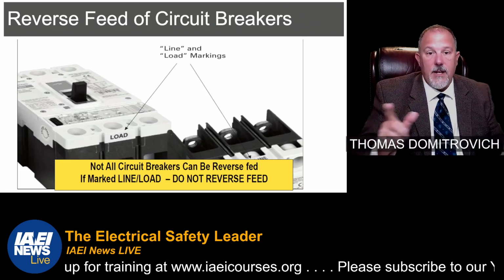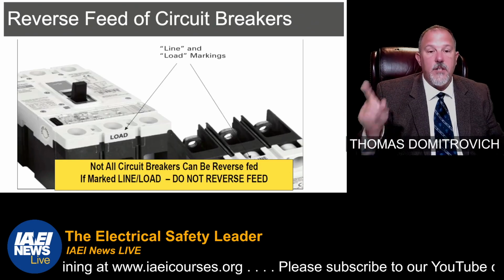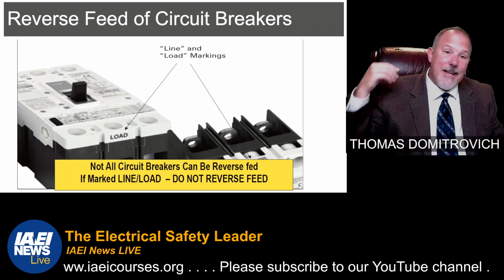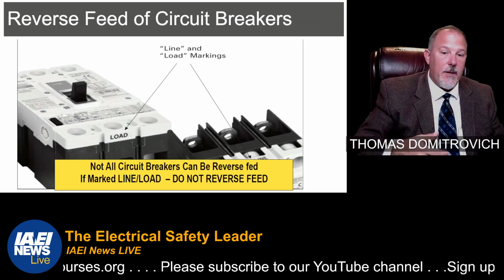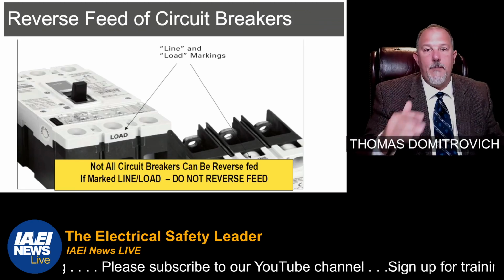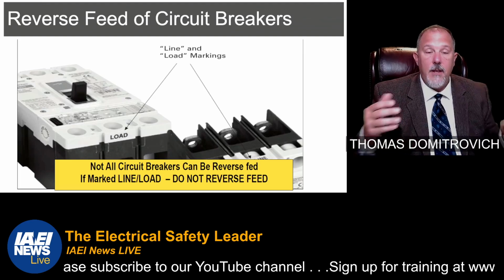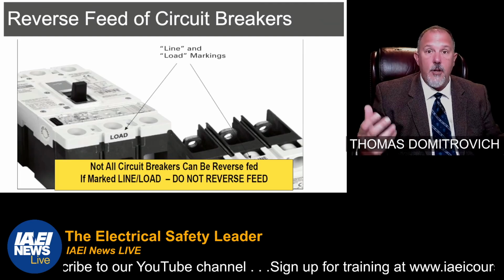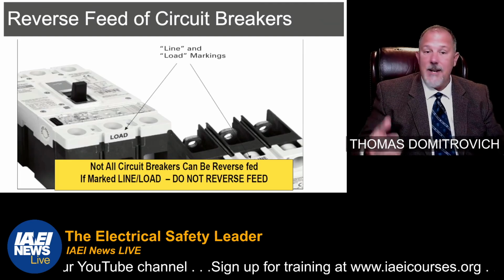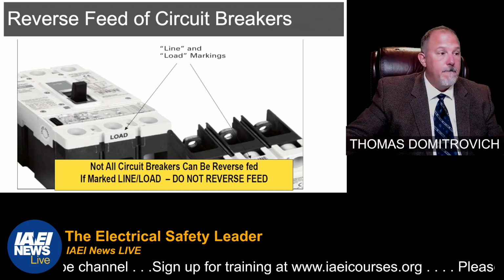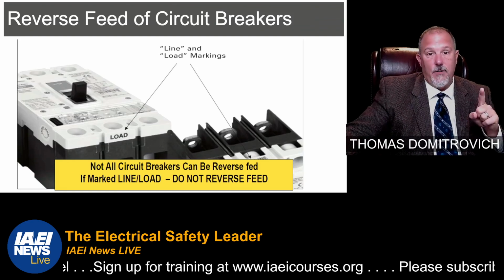Also keep in mind that if I have a circuit breaker that's marked line and load, I cannot backfeed that circuit breaker. Not all circuit breakers can be backfed, or switches. Anything that's marked line and load, that is one side is line, the other is load. Don't forget it.